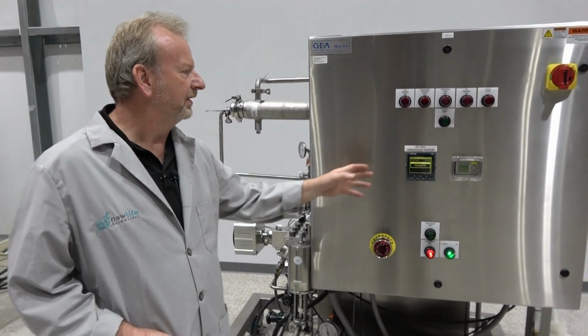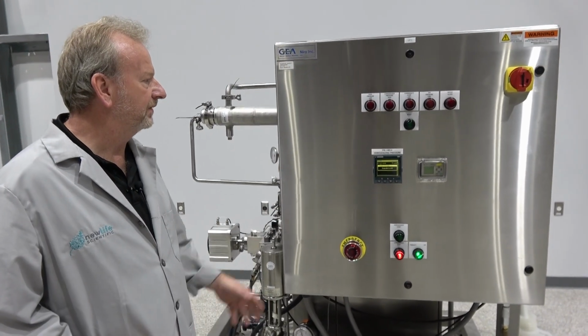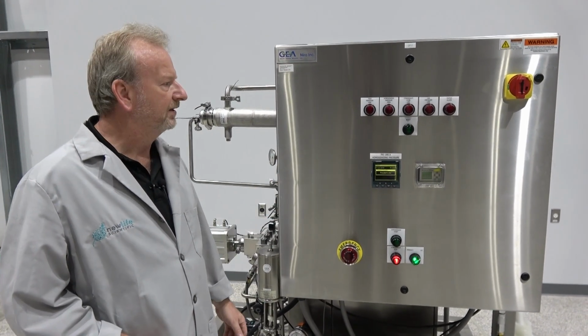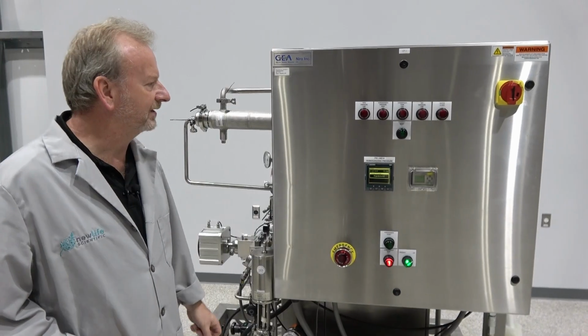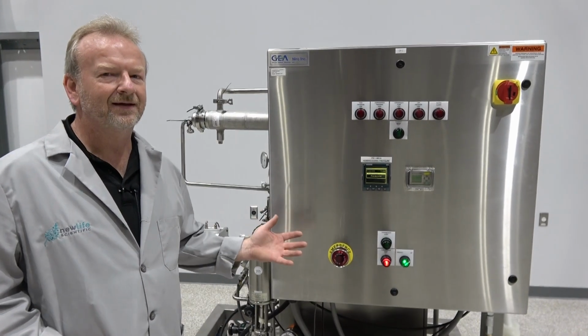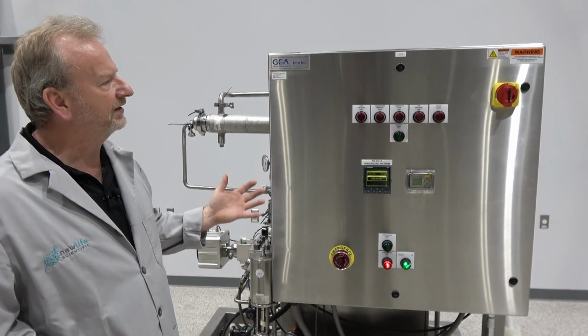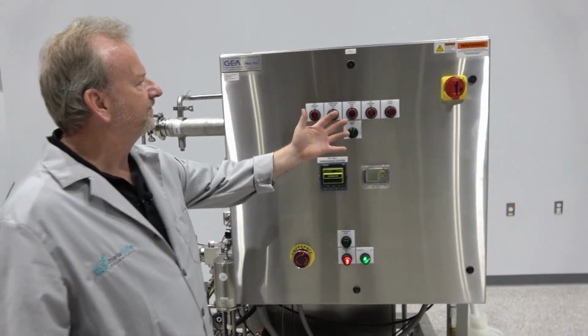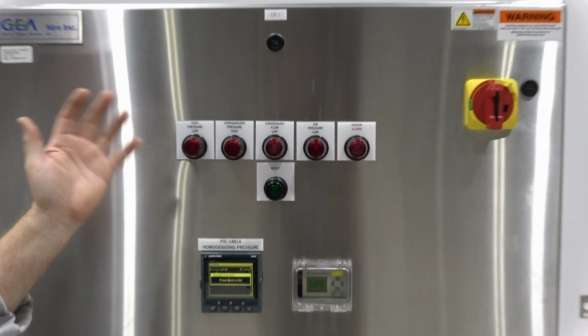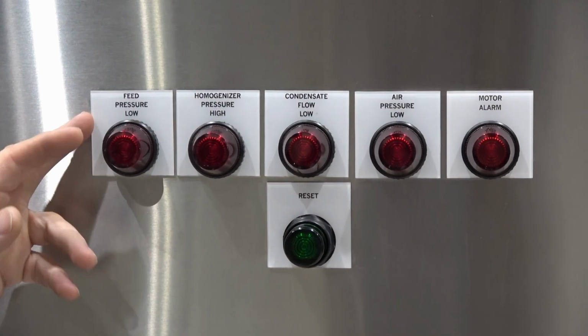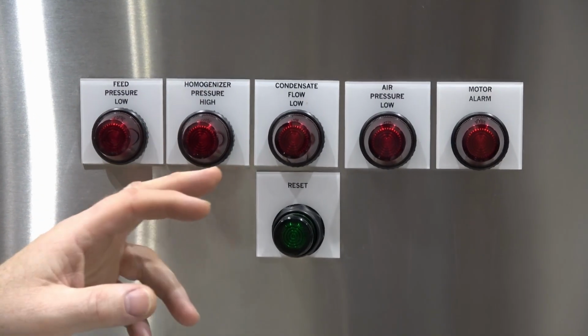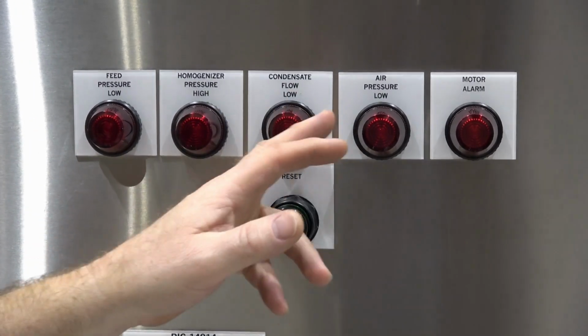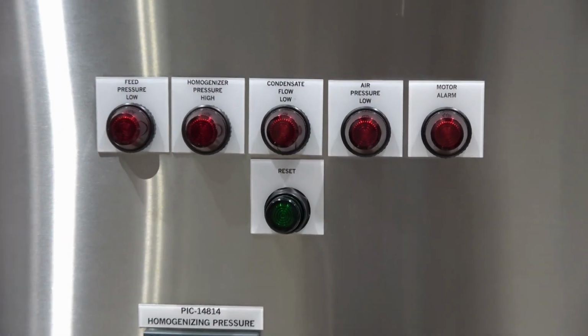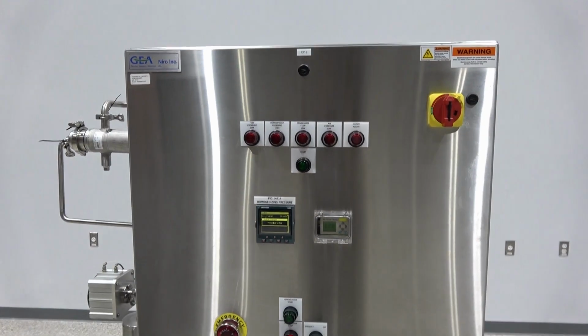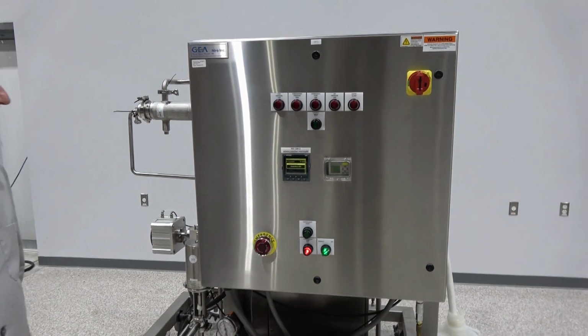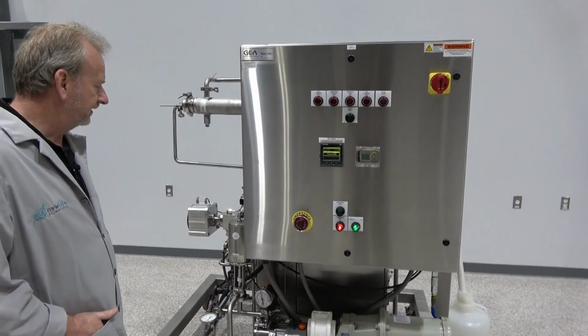This is still operable. It just would need a little bit more time to know how to program it and set your variables. And that's why I feel like it wasn't used, because there wasn't any programs in it when we got it, as if it wasn't even used. All the alarms are all working great. We've tested all the alarms. Your feed pressure works, your high pressure works, your condensate flow works, air pressure works. All these work. If you don't have everything it needs, it won't run, or it will shut down. So the safety features are all working great.